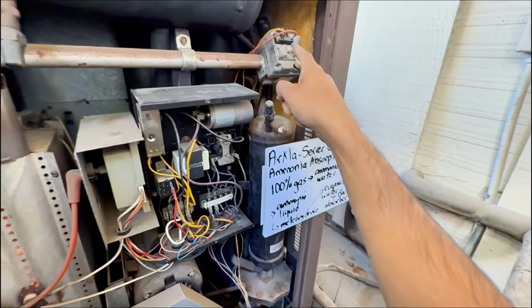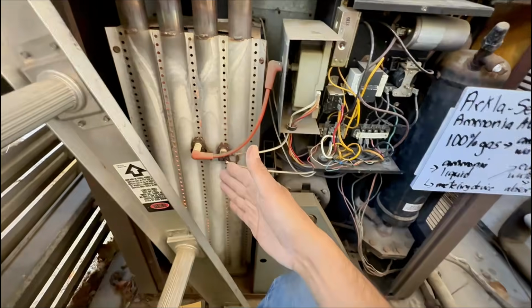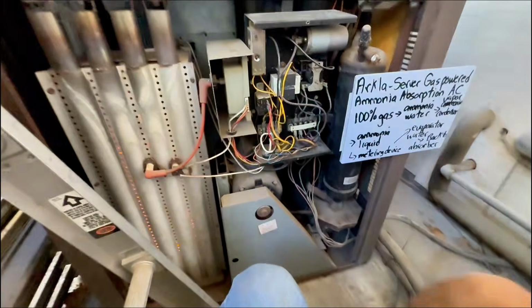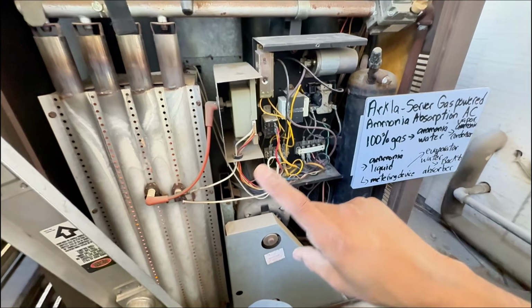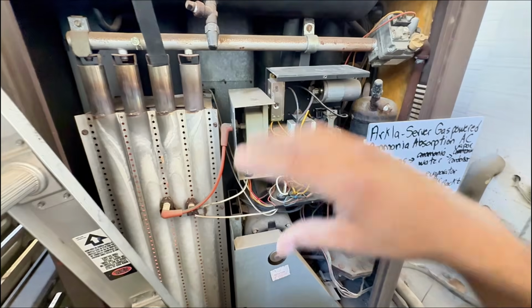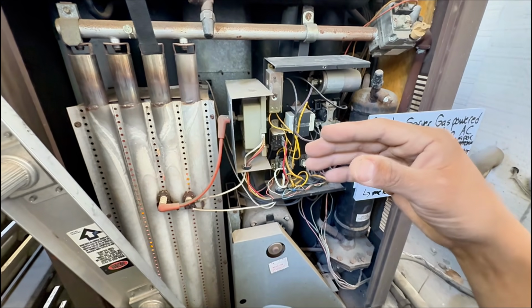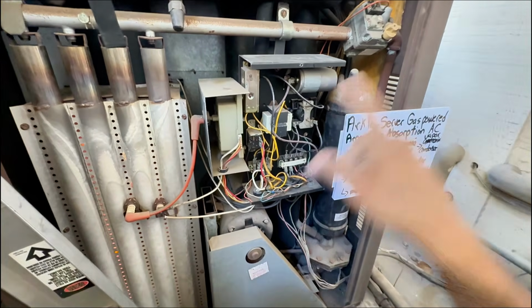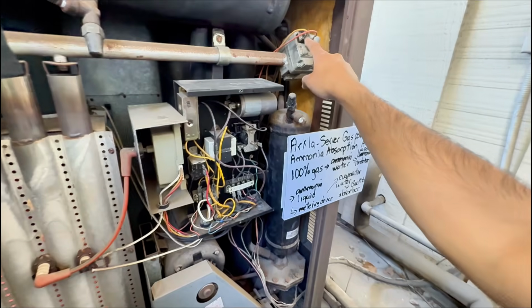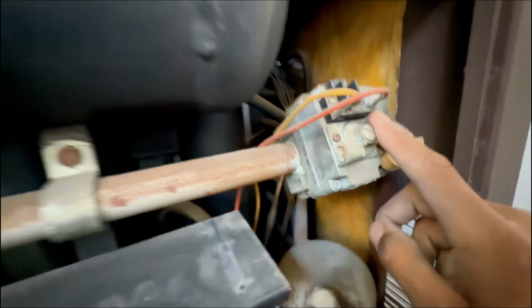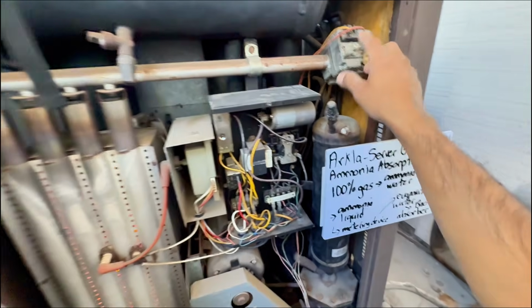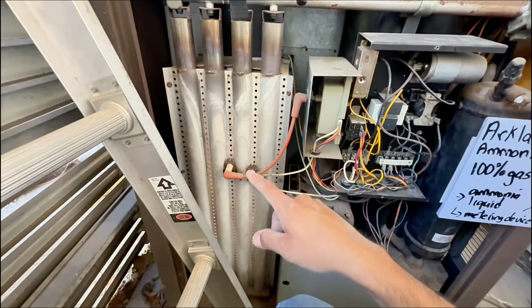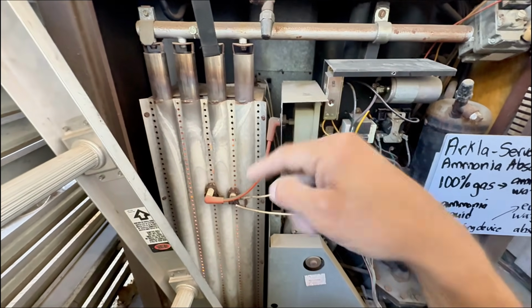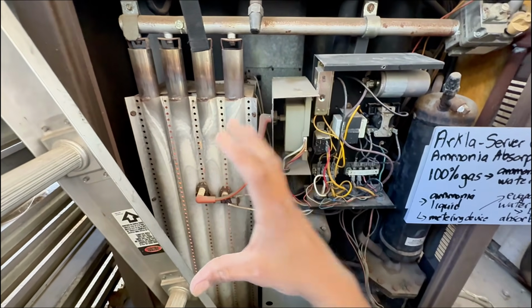Maybe there could have been a call for cooling, but you know what? Now it's on and it's working. I'm gonna go ahead and get a little clip of the inside so you can see the evaporator. But that was very interesting that now it's working. So I might clean off the, maybe it's very rusted right here, but I'm gonna go ahead and clean that up. I'm gonna check that I dropped the set point really low so that it stays on, and I wanna make sure it stays on, but honestly, it's working.